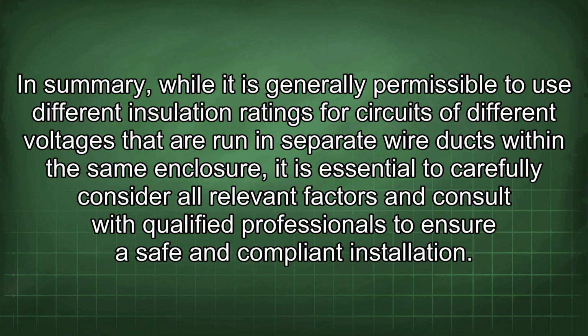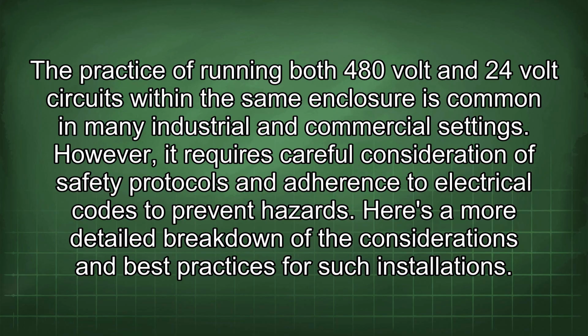In summary, while it is generally permissible to use different insulation ratings for circuits of different voltages that are run in separate wire ducts within the same enclosure, it is essential to carefully consider all relevant factors and consult with qualified professionals to ensure safe and compliant installation. The practice of running both 480-volt and 24-volt circuits within the same enclosure is common in many industrial and commercial settings. However, it requires careful consideration of safety protocols and adherence to electrical codes to prevent hazards. Here's a more detailed breakdown of the considerations and best practices for such installations.